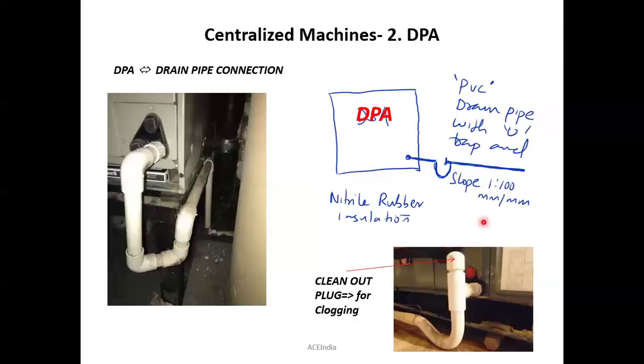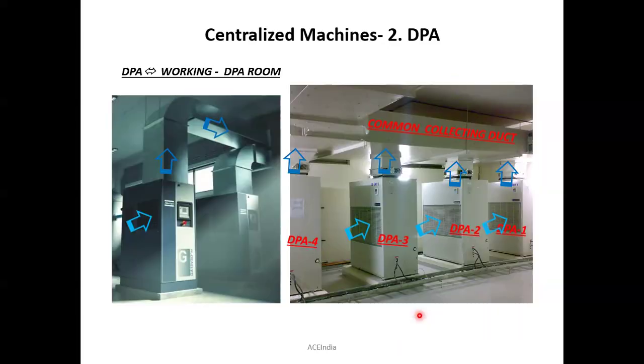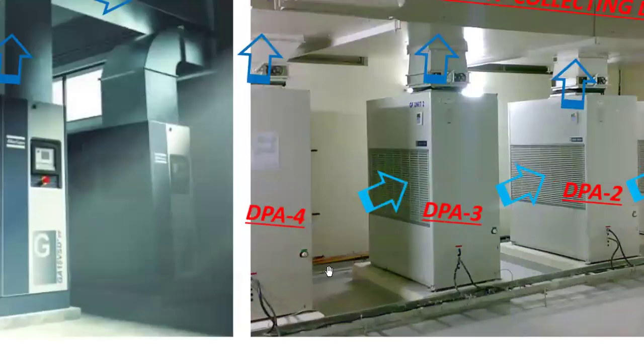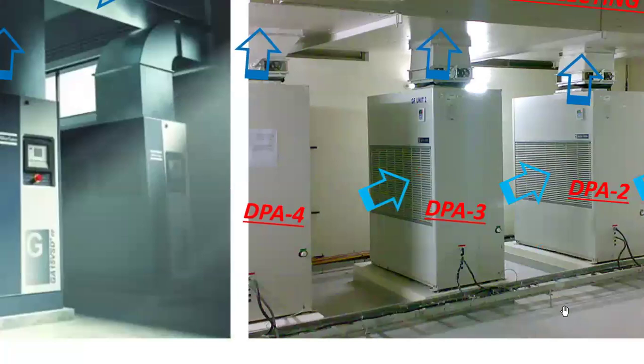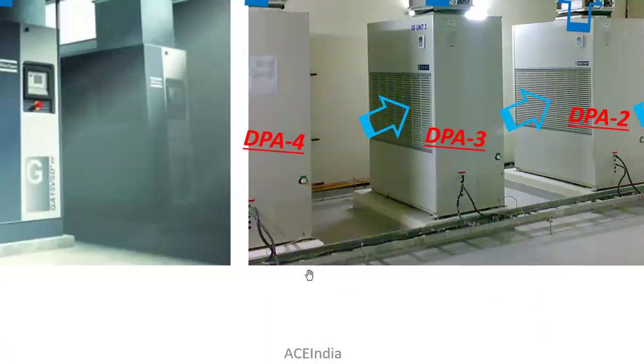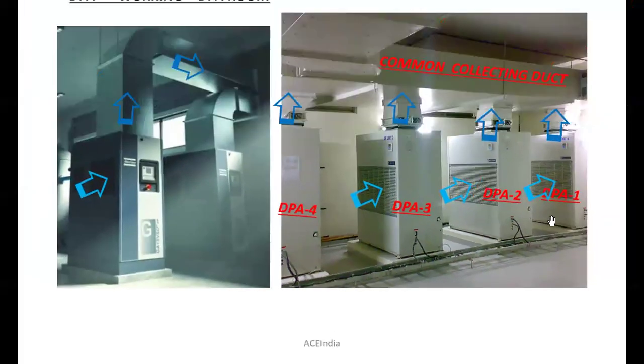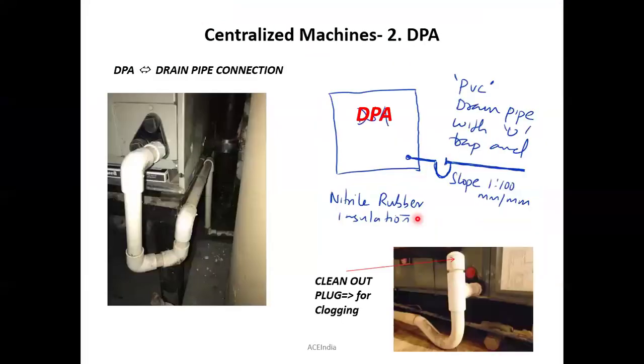Then the other connections are still the same, that means the drain pipe connection. You can see it right here now. This is how these drain pipe connections are done for a DPA. In this picture, you can see the copper pipes are railed this way by providing a small channel support, and on top of that the copper pipe connection is implemented. And this is how the electrical cable connections are provided. A proper ladder type cable tray is provided on the ground, and the electrical cables are laid across this cable tray, and the individual connections are made. Okay, now. So that's all about this one.